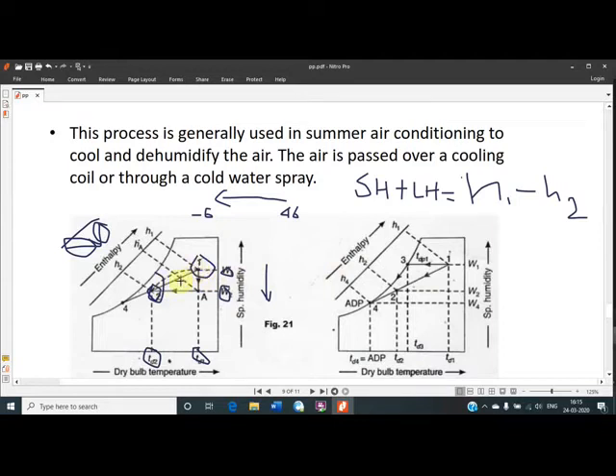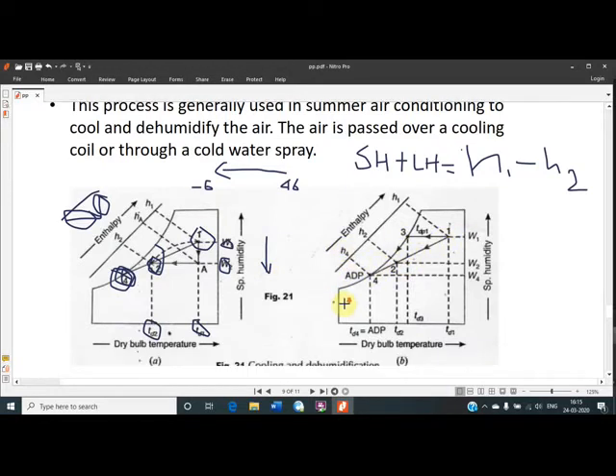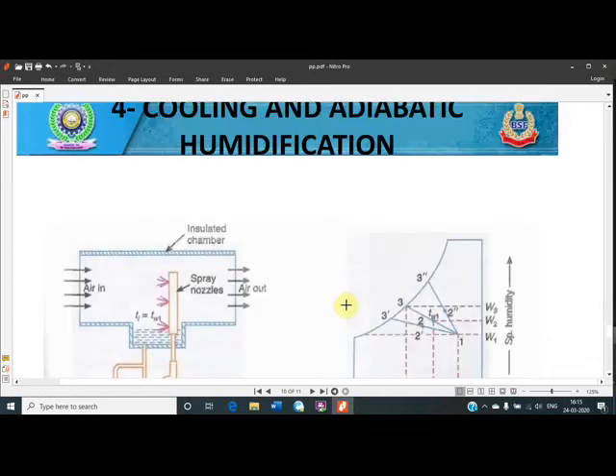Air enters at point 1 and leaves at point 2. The fourth point mentioned is the apparatus dew point temperature, which is the temperature of the coil. The air comes in contact with the coil at this temperature, but the final exit temperature is at point 2. This is how the cooling and dehumidification process is accomplished and takes place.